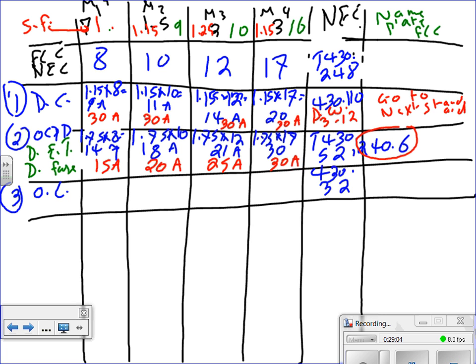Go to 430.32, guys. You're going to find the following. It tells you if the service factor of a motor is 1.15 or higher, your multiplier should be 1.25. In all other cases, your multiplier is going to be 1.15. Everybody saw that? Everybody read that?